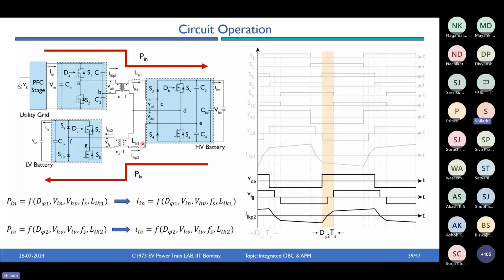This operating principle is summarized here. The actual expressions of power flow and current are quite complex, but functionally, your input current, or the power flowing through this transformer, is a function of d phi 1, and the power going to this output port is a function of d phi 2. So if you just change d phi 2, only that power changes, and if you just change d phi 1, this power changes — they do not affect each other.